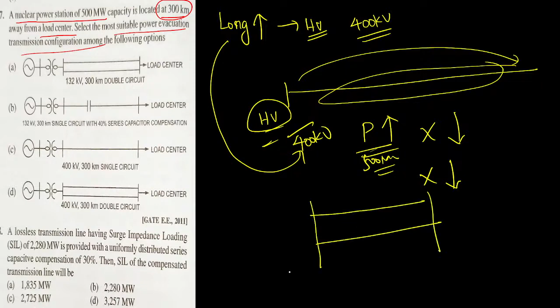Second thing, if you want to improve the power handling capacity of the transmission line, you must decrease the value of reactance. So the best preferable choice: first, since they gave a long transmission, we go with high voltage. Second, when we are transmitting high power, 500 megawatt, over a long transmission line, you must maintain a lower value of reactance. For that, instead of a single transmission line, if you select a double circuit line, what will happen? Single line reactance is X; with a double line, both are in parallel, so the net reactance will become X by 2. Power handling capacity of the transmission line will be improved. So the best choice for the long transmission line is a 400 kilovolt double circuit line. Now choose the answer.